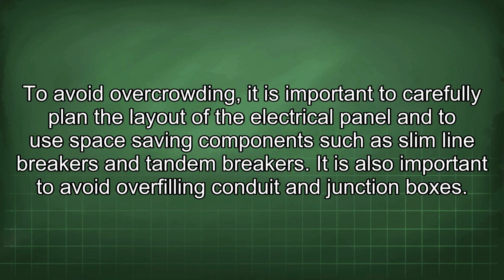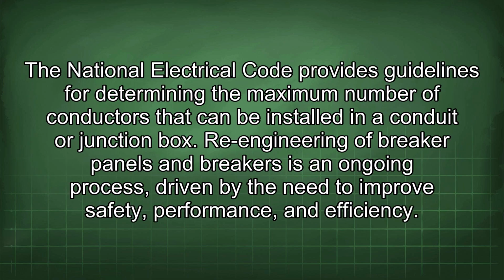To avoid overcrowding, it is important to carefully plan the layout of the electrical panel and to use space-saving components such as slimline breakers and tandem breakers. It is also important to avoid overfilling conduit and junction boxes. The National Electrical Code provides guidelines for determining the maximum number of conductors that can be installed in a conduit or junction box.